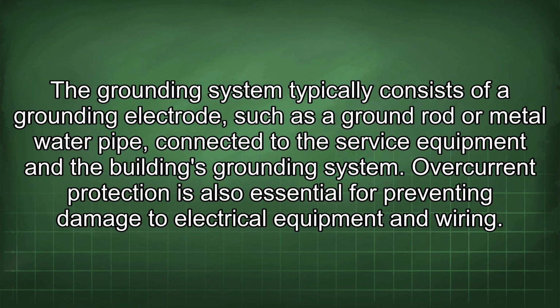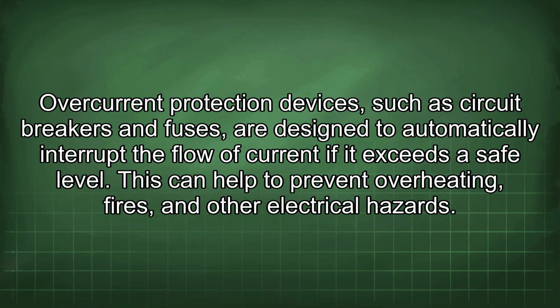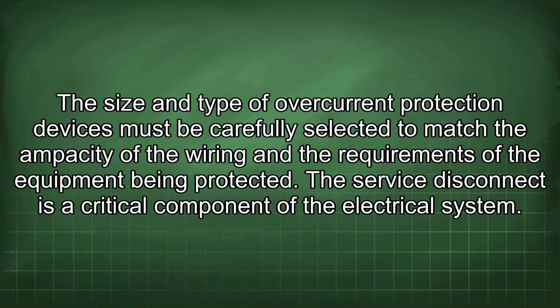Overcurrent protection is also essential for preventing damage to electrical equipment and wiring. Overcurrent protection devices, such as circuit breakers and fuses, are designed to automatically interrupt the flow of current if it exceeds a safe level. This can help to prevent overheating, fires, and other electrical hazards. The size and type of overcurrent protection devices must be carefully selected to match the ampacity of the wiring and the requirements of the equipment being protected.